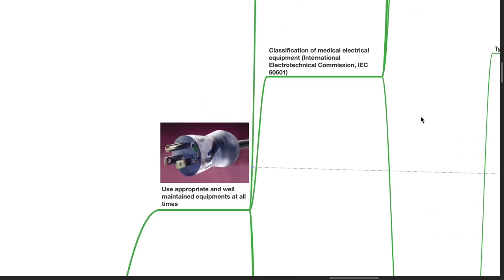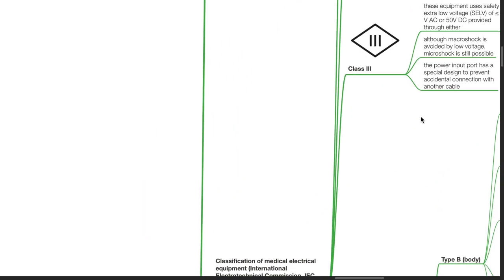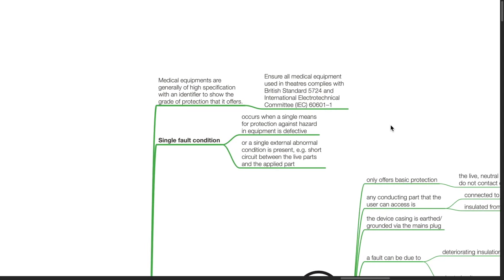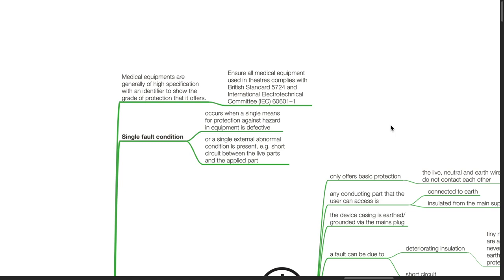Use appropriate and well-maintained equipment at all times. Medical equipment should comply with British Standard 5724 and International Electro-Technical Committee IEC 60601-1. A single fault condition occurs when a single means of protection is defective or a single external abnormal condition is present, such as short-circuit between live parts and the applied part.